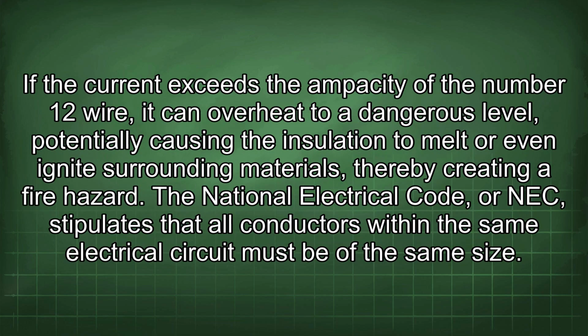If the current exceeds the ampacity of the number 12 wire, it can overheat to a dangerous level, potentially causing the insulation to melt or even ignite surrounding materials, thereby creating a fire hazard.